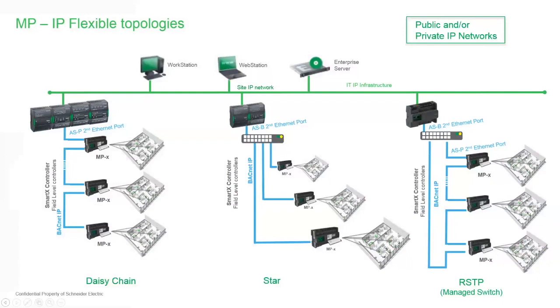Then on the end we've got a ring topology. More or less, the ring topology lets us hit every other controller on the way out and every other controller on the way back, so if I lose the middle controller, I can still connect to everything upstream and downstream of it—I just lose that one controller. It's a nice hybrid approach.